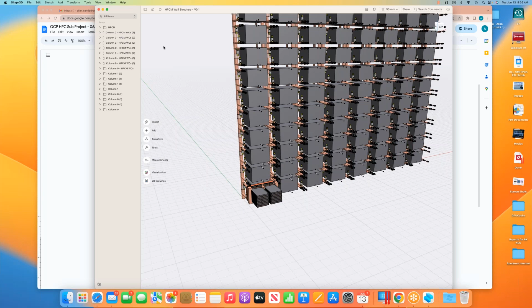Maybe, seeing we've got a bunch of thermal people on, I'll open up the module itself so you can see what we've changed on the module. One of the things with this approach - I'm thinking we may need to make the module maybe up to 10 millimeters wider, so go from 102 to 112 millimeters, because the copper between the modules for picking up the conductive cooling is a little bit thin - less than a millimeter thick. So by the time you put an interconnect in there...